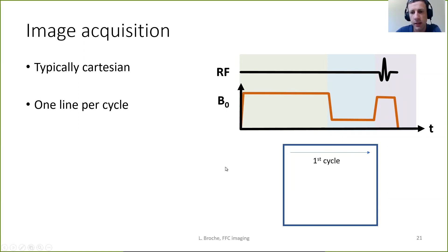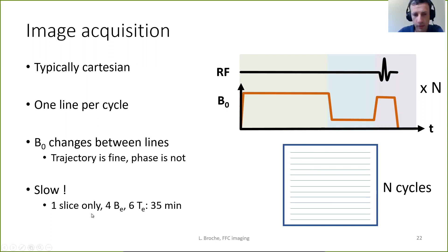The trajectory is actually correct, accurate. We have a problem with phase. I'm going to come back to that. And of course, it's a bit slow. We can only image one slice at a time for a volume. We can only probe 4 fields and 6 evolution times in 35 minutes. It's difficult to go for longer than 35 minutes because we need to install the patients, get scout images, and so on. So typically, that's the kind of examination we have.